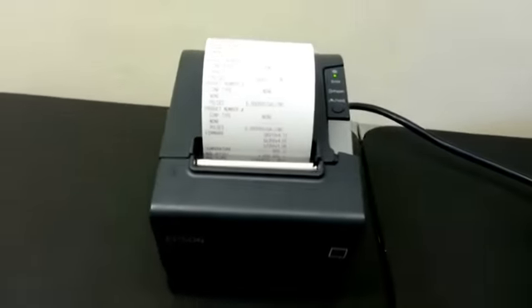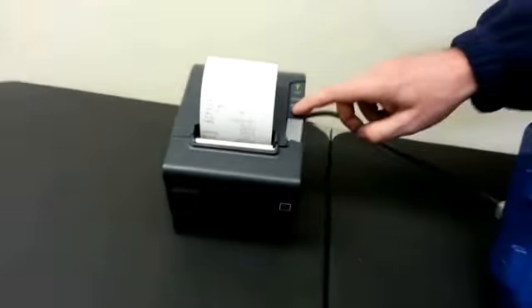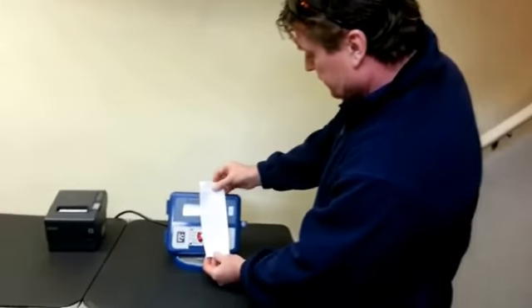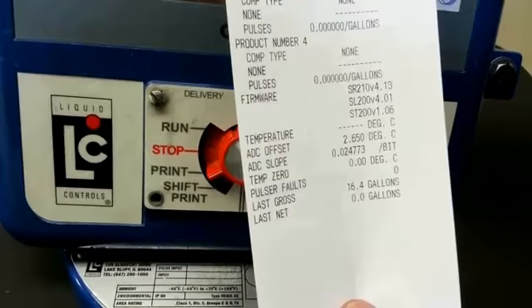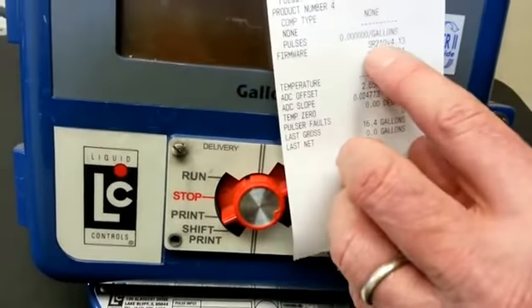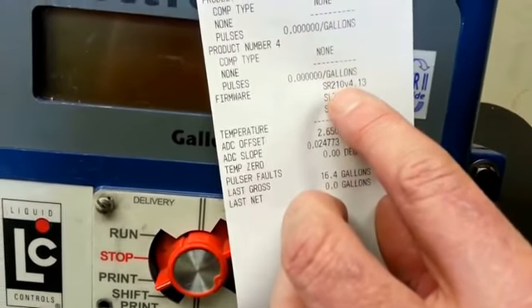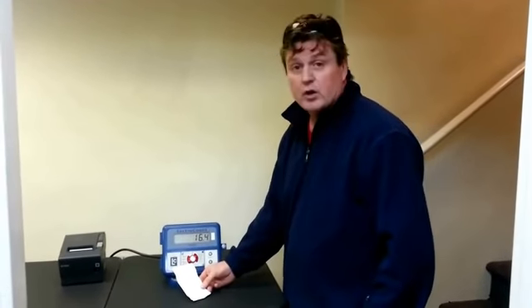What I'm using here is a roll printer, but you can run the same report with a slip printer. Once the report's done, you remove it from the printer and take a close look, and this will tell you the firmware version. Right here, we've got firmware version SR210v4.13. The LCR firmware version you want running should be at least SR210v4.0 or later, and this covers all LCRs manufactured in at least the last 10 to 12 years.